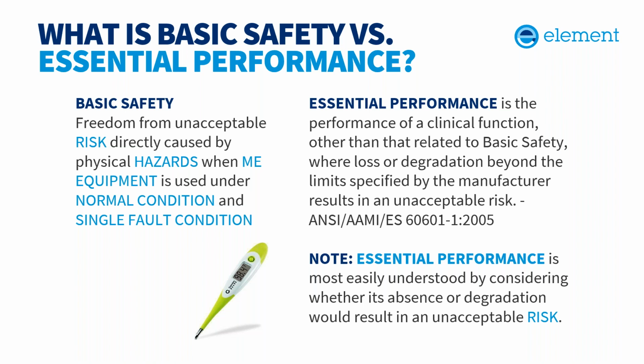So on the other side is essential performance. Essential performance covers the functions of the system. Does a pacemaker keep pacing? Does an ablation generator deliver therapy? Would a risk to the health of the patient occur if the performance was degraded? So for some medical devices, immunity tests may need to be run twice, once to monitor basic safety and once to monitor essential performance.